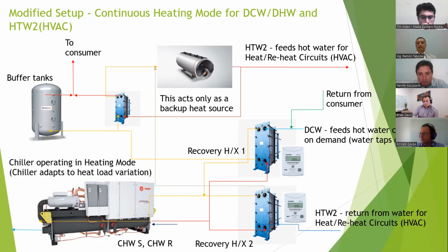At the time, I was not aware that chillers of this size, talking about 1.2 megawatts, exist that can operate in heat pump mode and go beyond 50 degrees. Basically, these chillers go up to 68 degrees Celsius. So I had to sit down, redesign the whole system, and integrate the new chillers. So basically, we end up with this system.